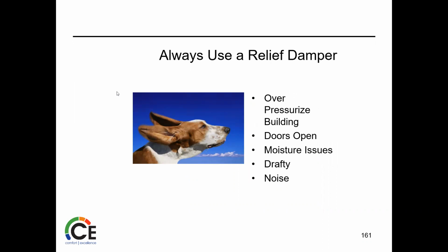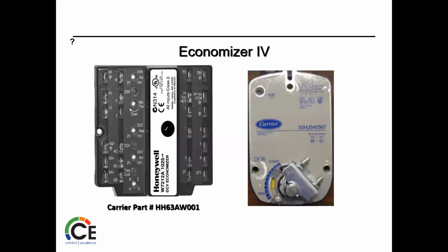They always talk about making sure you're using a relief damper, especially if you don't want to over pressurize the building, because then doors are slamming and carrying on. Doors open, moisture issues, drafty, noise, those types of things. If you've been on a roof, I think you know this control's been around for about 20,000 years, I think. Actuators really haven't changed all that much. They still pretty much look the same. It's not an overly complicated control. It can be a little confusing, again, if you've never done it.